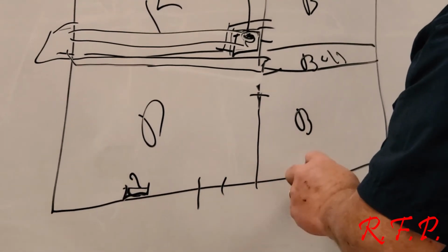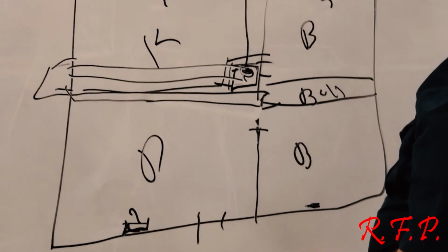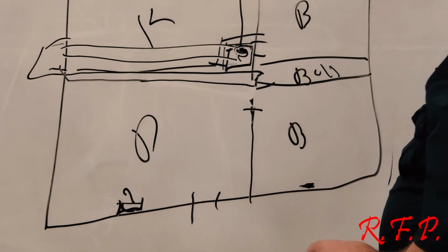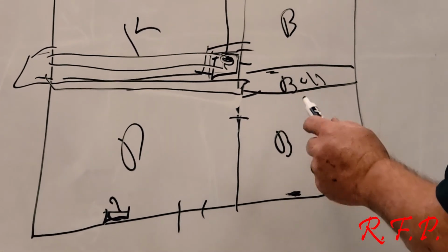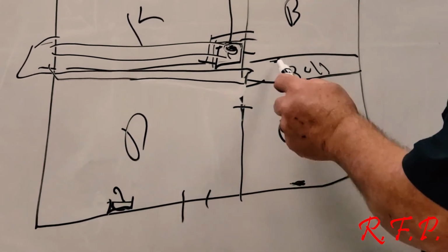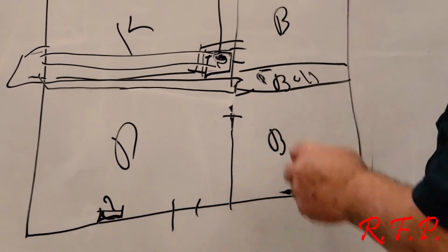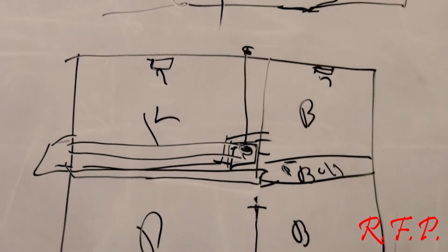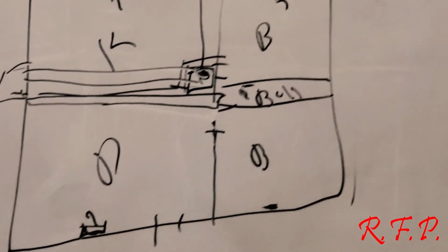4 7s is 150 each. 4 7s is 600 CFMs. Is that right? So if it's a 2-ton, I needed 800. I put 4 7s and a 5 on it, or a 6. Let's just say that that's a 6 in the bathroom, and I got 700 CFM. Can I live with that on a 2-ton package all day long? All day long.